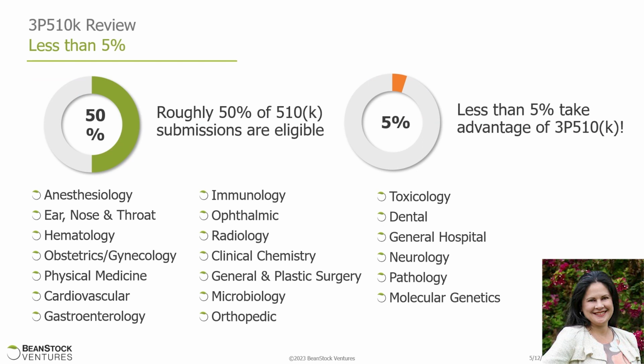This is an interesting statistic, which I don't think a lot of people are aware of, but roughly 50% of 510K product codes are eligible for the third-party review program. And there's less than 5% that actually take advantage of this program. Why, we don't know. I think some of it might have to do with trust, familiarity with the program, visibility, understanding the program. So that's why I'm presenting this today, to give you an overview of what the program really involves and the ins and outs of it.